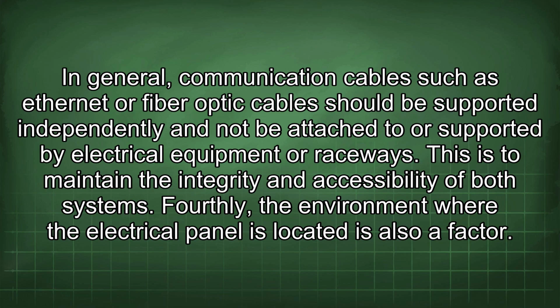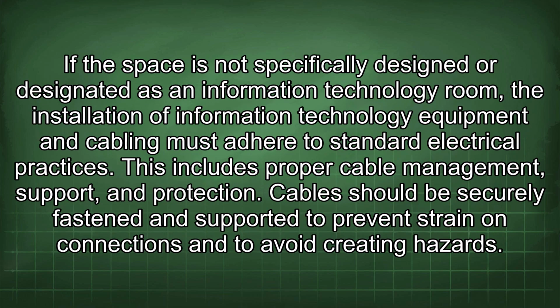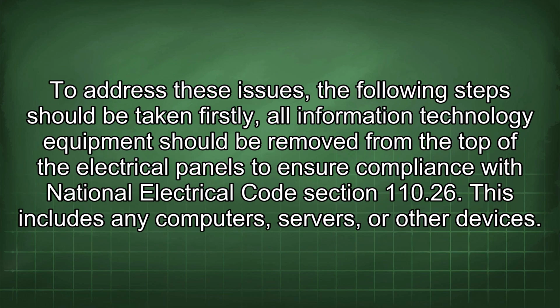Fourthly, the environment where the electrical panel is located is also a factor. If the space is not specifically designed or designated as an information technology room, the installation of information technology equipment and cabling must adhere to standard electrical practices. This includes proper cable management, support, and protection. Cables should be securely fastened and supported to prevent strain on connections and to avoid creating hazards. To address these issues, the following steps should be taken.